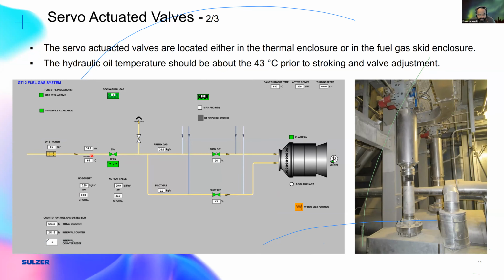So after your ESV, you will have your premix control valve and your pilot control valve here. And whenever you shut down and both valves are closed, you realize there is what you call a natural gas unloading valve or a purge valve. Now, this is not too old. Actually, this is one of the norms, I believe, that came in the 80s, because accidents occurred and the design had to be changed, because when you shut down, even though it's a small pipe segment, you have trapped gas in here up to 21 bar, or in this case 39 bar.